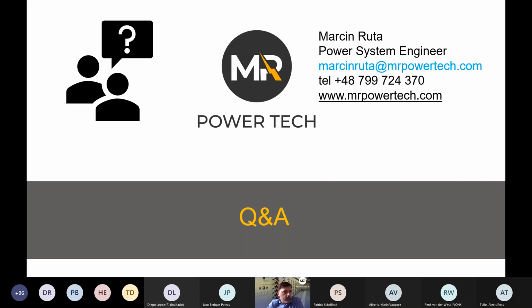You mentioned a 5 year review requirement, which raises a question about the legislation or jurisdiction that applies. Is this 5 year review period part of legislation? Does it apply in the US, Europe, the rest of the world? To be honest, I don't know. 5 years is a given value in NFPA, which requires reviewing the study every 5 years as a maximum time. The background is that 5 years is enough time in industry for things to change.